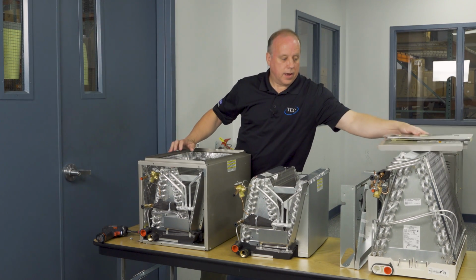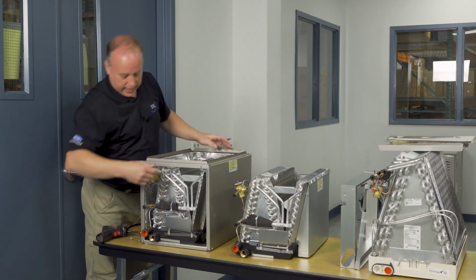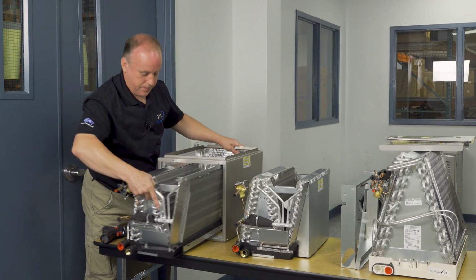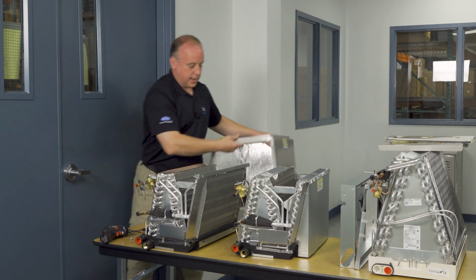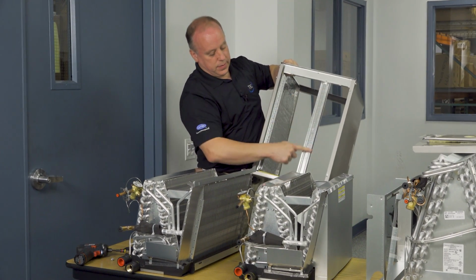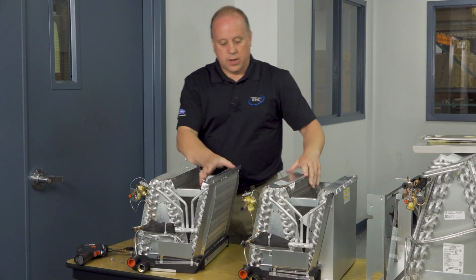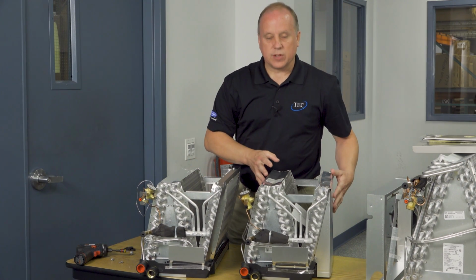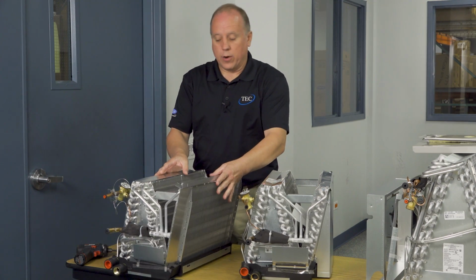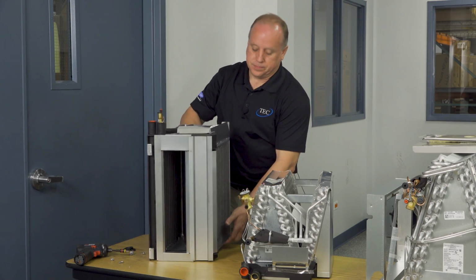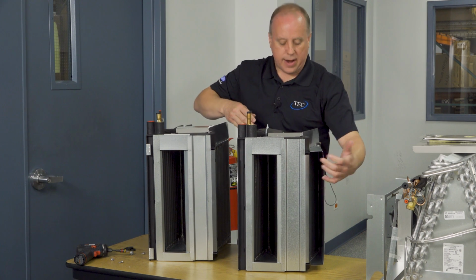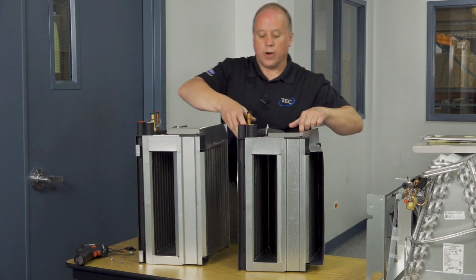in an uncased application. So I've got everything out and free, so I just got to work my coil out of the case. I'll slide that out. I'm going to set the case down to the side here. As we see, we've got a rail on the bottom because of the end design on the coil. So if we look at both of these coils, they look a little bit different. On this side we have this baffle. This side we're wide open. So if we look from the bottom, we could see how this baffle on this side is going to capture the air and make sure we get through the end side of this coil.